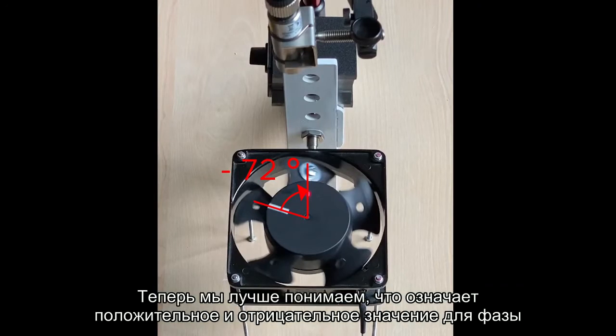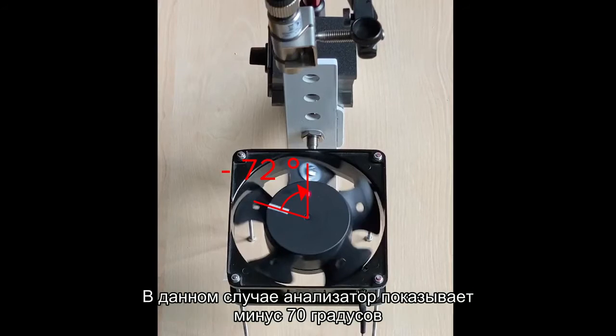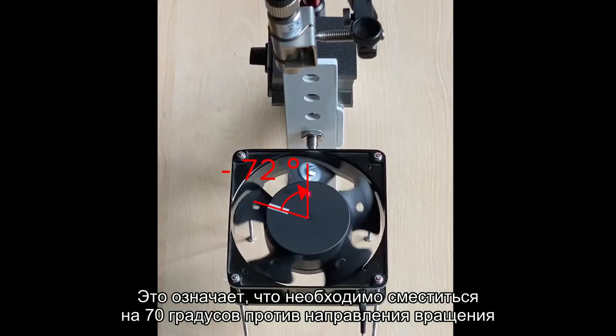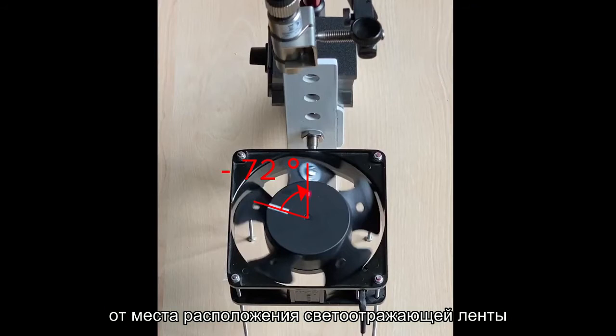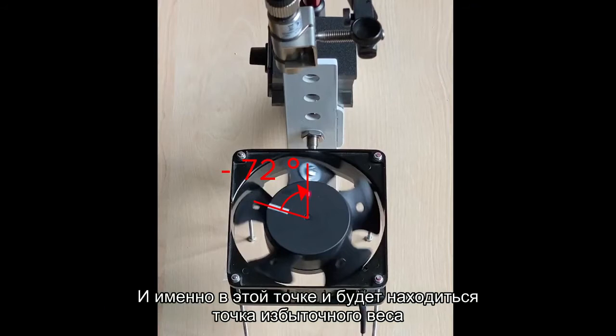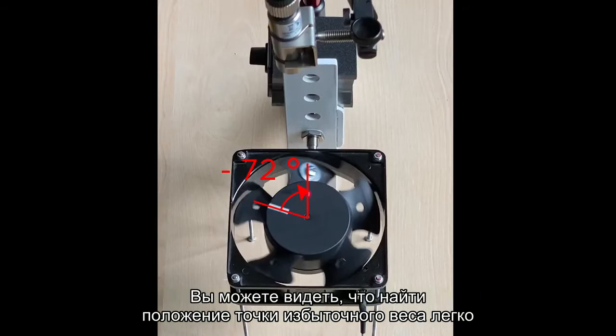Now we better understand the plus and minus direction of phase. The analyzer displays minus 70 degrees in this case. It means we have to go 70 degrees against the rotation direction from the reflective tape position. And in this position the heavy spot is. You can see that it is easy to find the heavy spot position.